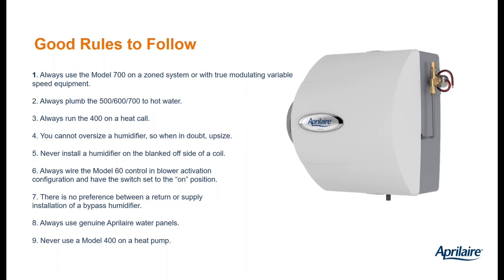Our three flow-through evaporative humidifiers, the 500, 600, and 700, and of course the 500M, 600M, and 700M, we always want to plumb those to hot water. That hot water will always give us more evaporation when there's a heat call, and it even gives us the ability to evaporate when just the HVAC blower is running. That's important. The Model 400, because it has those small reservoirs inside, is not a flow-through unit, so the hot water doesn't really give you any benefit. So typically you plumb that to cold water, because the water sitting in those reservoirs is going to have time to cool off to room temperature. That's why. So it's really only going to give you good evaporation during an actual heat call.